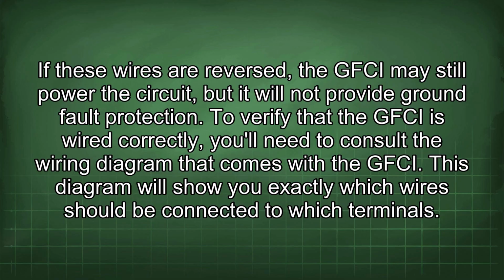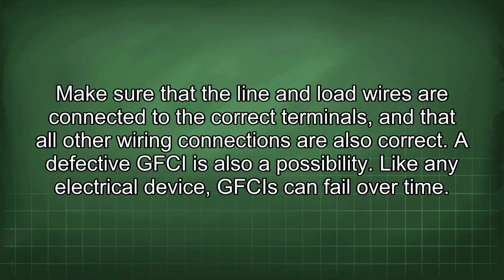To verify that the GFCI is wired correctly, you'll need to consult the wiring diagram that comes with the GFCI. This diagram will show you exactly which wires should be connected to which terminals. Make sure that the line and load wires are connected to the correct terminals, and that all other wiring connections are also correct. A defective GFCI is also a possibility. Like any electrical device, GFCIs can fail over time.